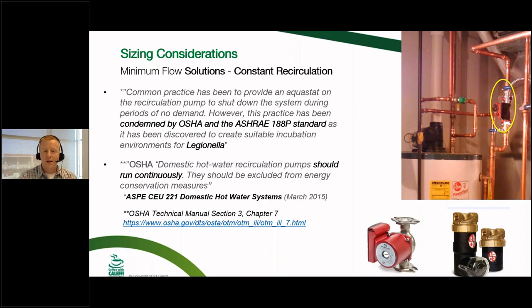And not only did they come out and condemn aquastats, but they went so far as to say that pumps should run continuously and should be excluded from energy conservation measures, which I think is a pretty strong statement. And hopefully that all comes true, and the use of aquastats will go the way of the dodo. So again, whether it be a high-low or continuous recirculation, if that continuous recirc is meeting the minimum flow requirements for the valve, you don't have to have that huge demand from the fixtures anymore. You can count on that recirc to meet that minimum flow for you.